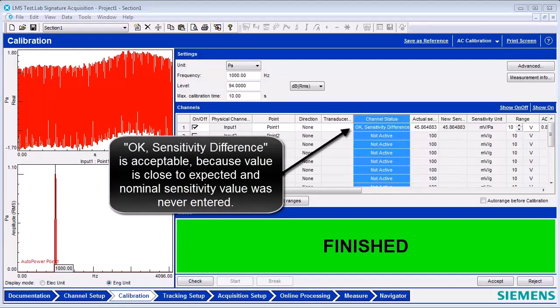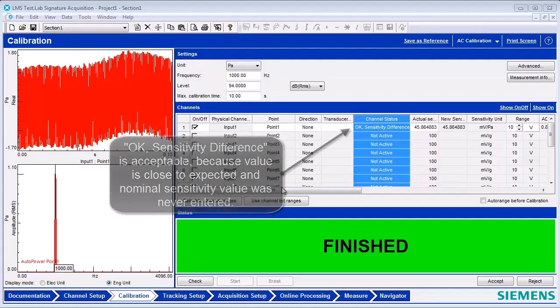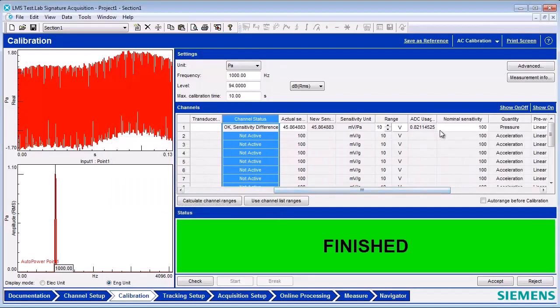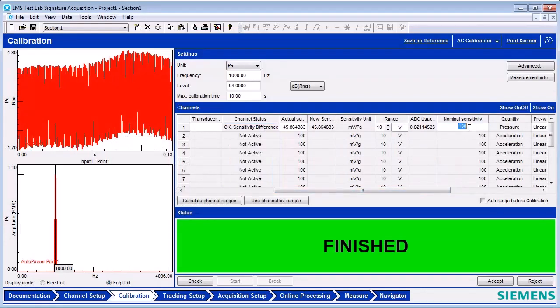In order to change the field called Nominal Sensitivity, scroll to the right in the Calibration Worksheet Channel section. Change the value from 100 to 45.